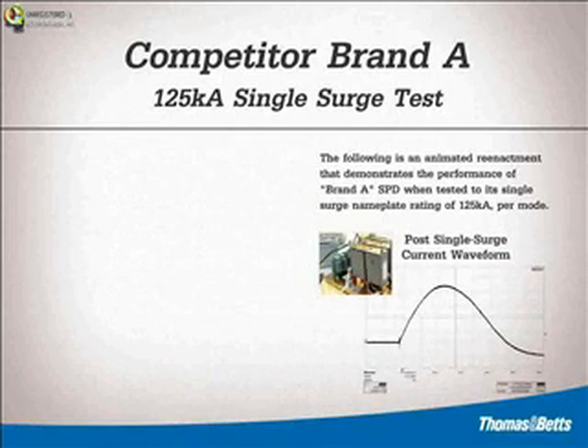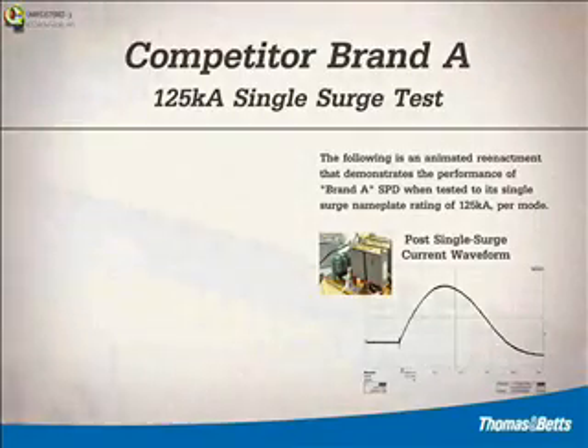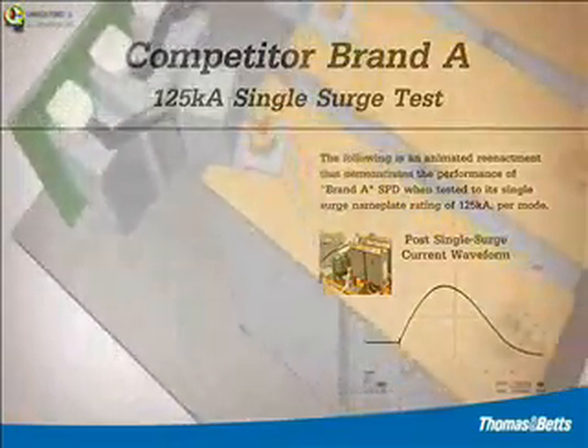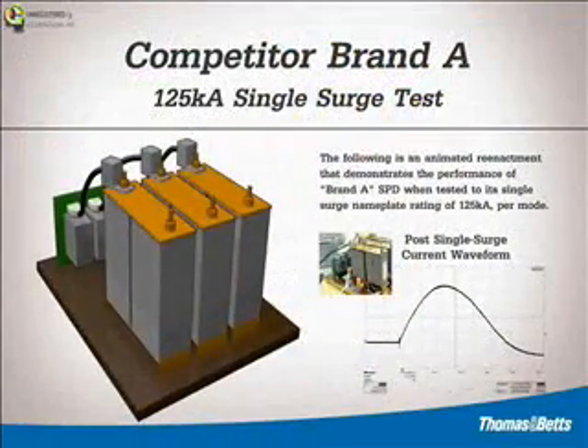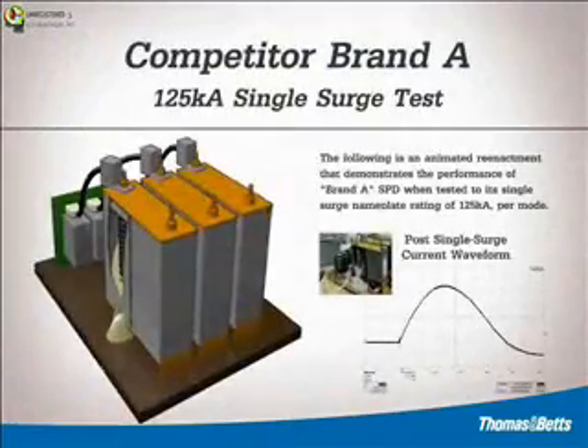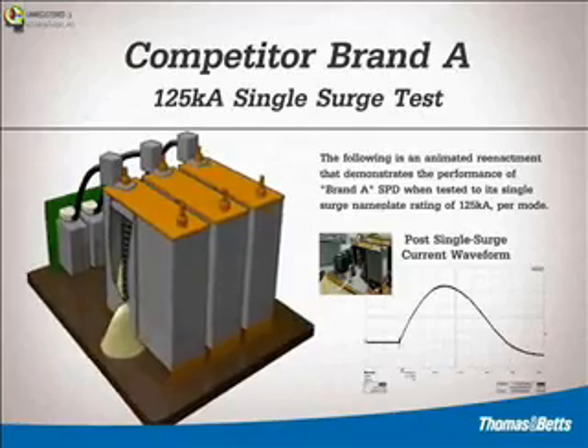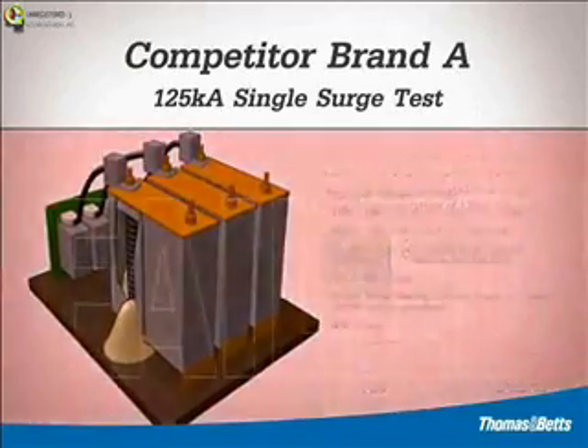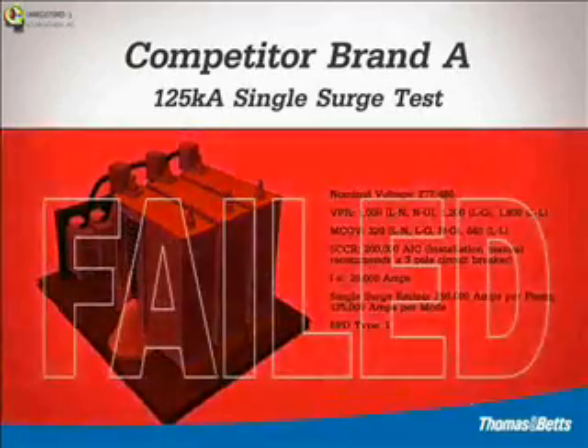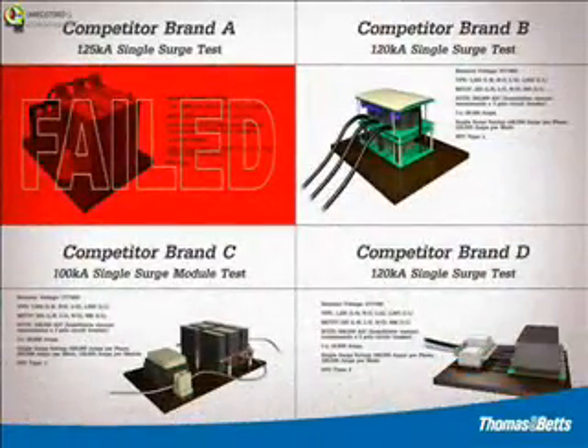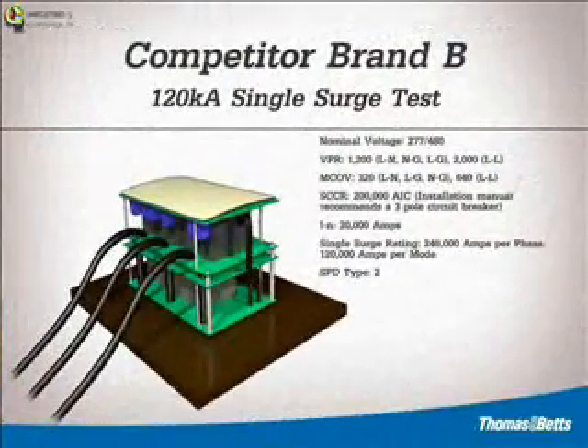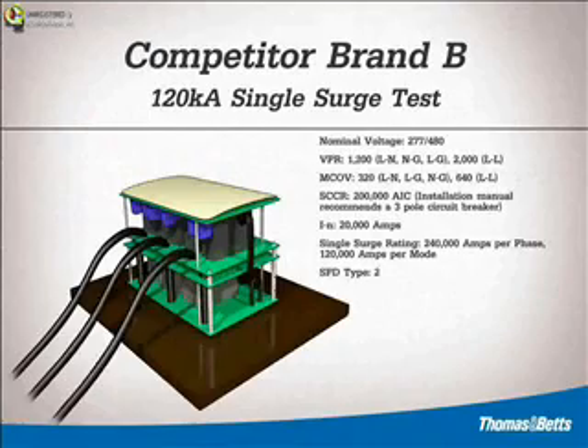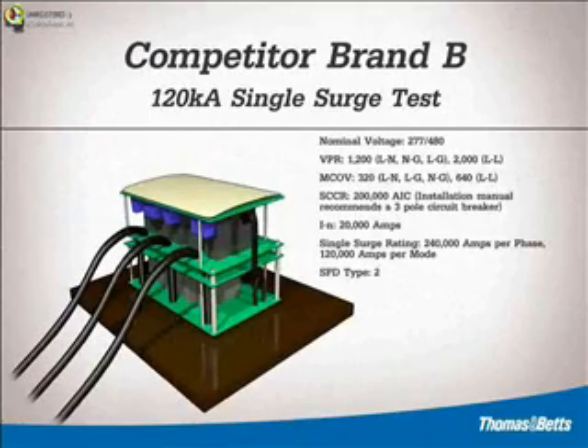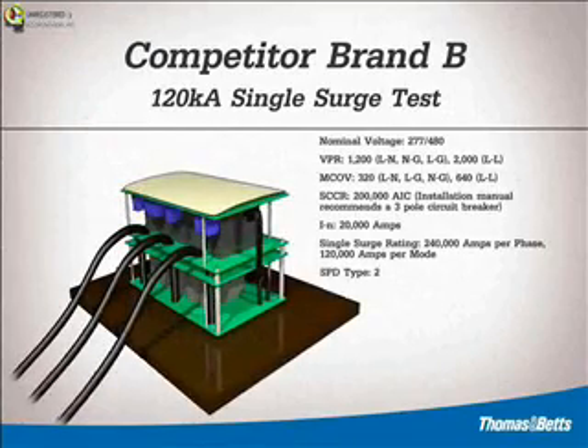The following is an animated reenactment that demonstrates the performance of Brand A SPD when tested to its single surge nameplate rating, 125 kA per mode. The background audio you hear is actual and validates the destructive outcome of this test. Samples B, C, and D also failed when subjected to a single surge at their marketed values. Although they failed in a safe manner, they were no longer functioning and would need to be replaced.